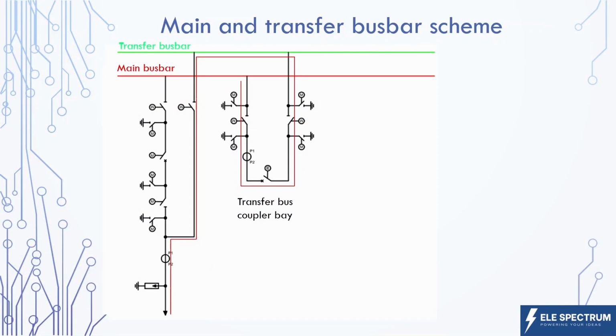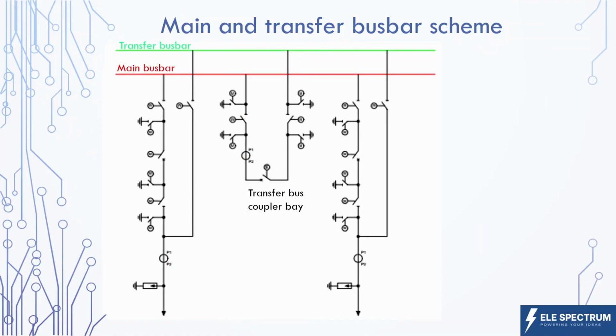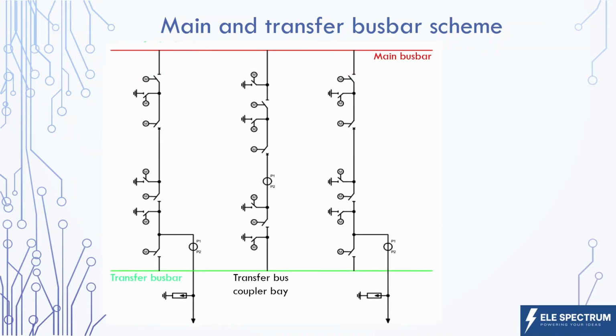Please remember that we are using the transfer bus coupler bay only in case we want to maintain a particular breaker. Otherwise, this transfer bus coupler bay is not operated during normal operation and all the feeders are connected to the main bus bar directly through the main circuit breaker. So we can have multiple feeders connected to the main bus bar and we will have one transfer bus coupler bay in the entire substation for this main and transfer bus bar scheme. Now we can also represent this single line diagram in another way which is more common. So we will just be shifting this transfer bus bar to the bottom of this single line diagram. So the arrangement remains the same, but the only thing is we are representing the main bus bar on top and the transfer bus bar on the bottom. Let's see the advantages and disadvantages of this bus bar scheme.